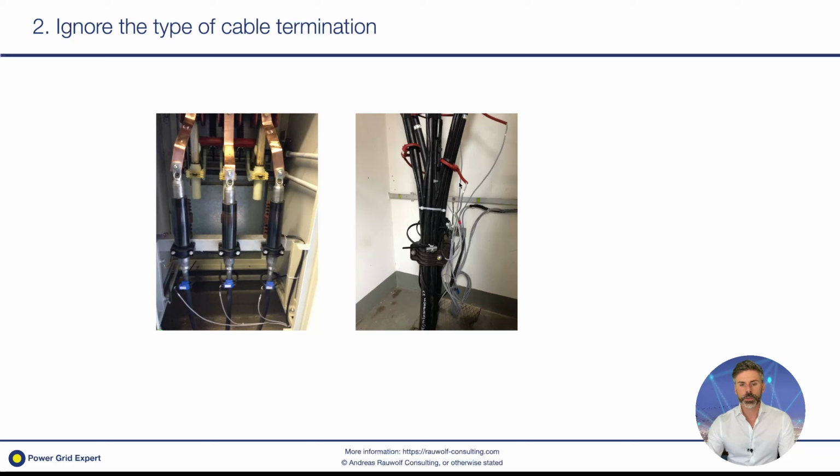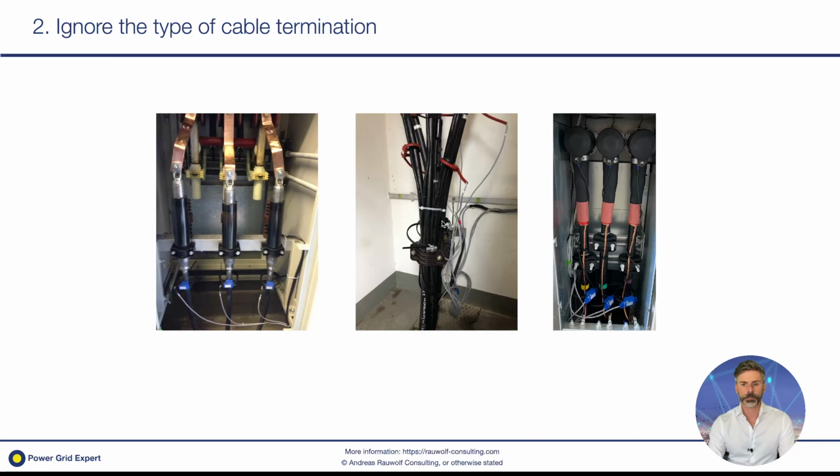That's another example. This is a quite modern plastic cable, 3-core. So we see here the 3-core cable coming in, then the 3 phases are coming out. Here you can see there are still screens, so no problem here. You can install them easily on that part. And that's the most modern and most common version. Elbow plug, plastic cable, black area here with a screen, no problem to install.